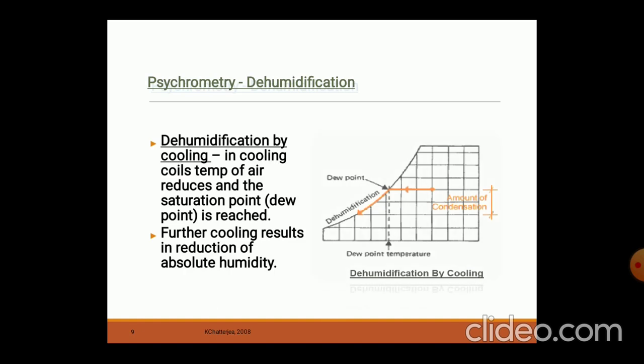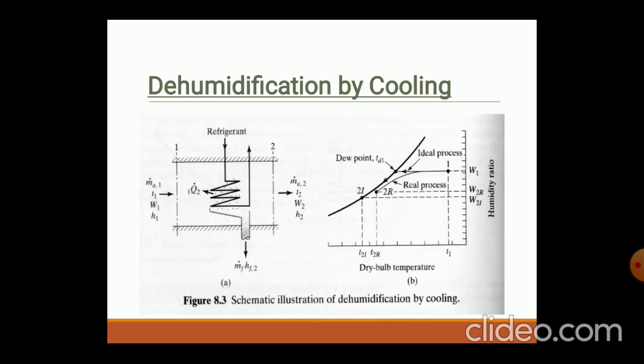Dehumidification is achieved with the help of cooling — dehumidification with cooling. In the cooling coils, the temperature of air is reduced and the saturation point, which we call the dew point, is reached. This is represented on the psychrometric chart. The further cooling results in a reduction of absolute humidity. Dehumidification by cooling is achieved through the refrigerant in the coil, and on the psychrometric chart we can see the dry bulb temperature — this is the illustration of dehumidification by cooling.